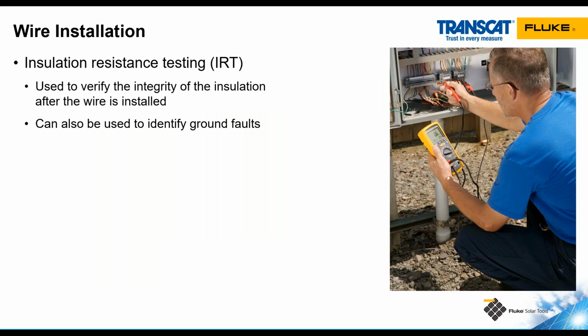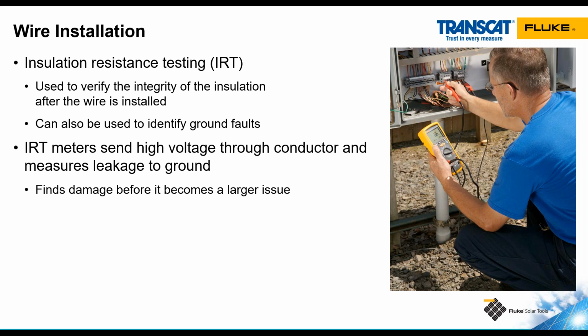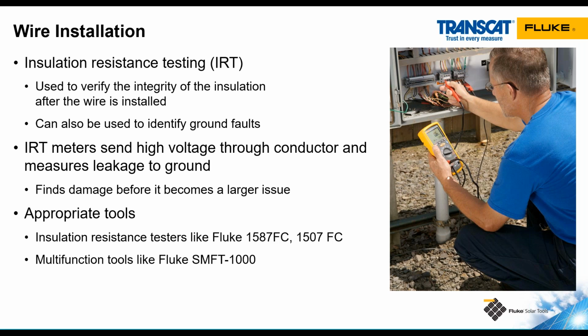In the installation phase, a really good test to perform is insulation resistance testing. We're doing this to make sure that the insulation of the wire was not compromised. We can also use this type of testing to identify ground faults, both during installation, at commissioning, and in operations and maintenance as well. What we're doing is essentially charging the wire. The wire needs to be disconnected from any other components, especially electrical components. We're going to send a high voltage, low current charge into that wire and see if there's any current leaking to ground.